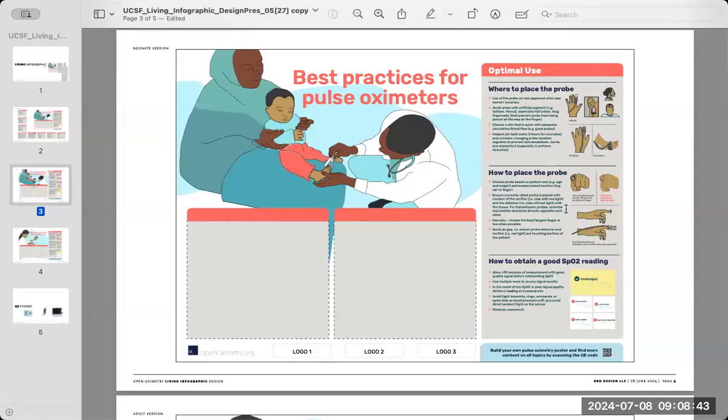Since we have a moment, it sounds like maybe can you just describe better placement, not the toe? What would it be better to illustrate that with? Great toe is no good. The large toe. Okay. Right. So another toe works just fine, but they typically have a wrap sensor. It's rare that you would be using a clip on a baby, or in this situation, an infant. Rather, it would be on a larger child, and then you could get away with that in surgery.